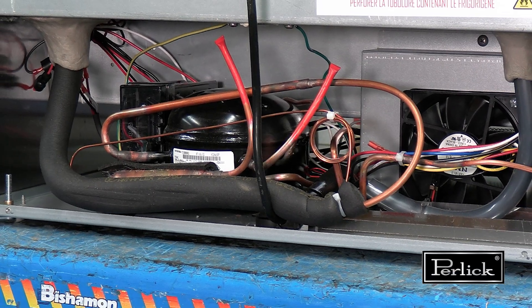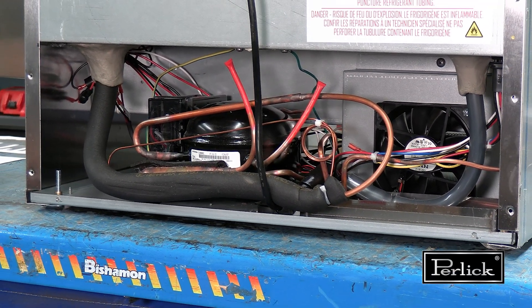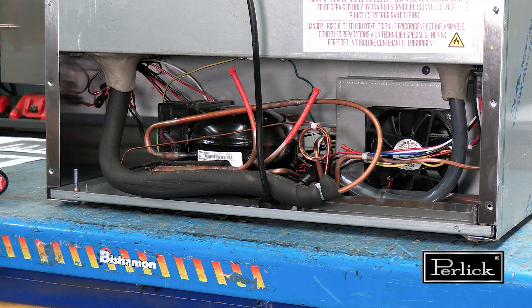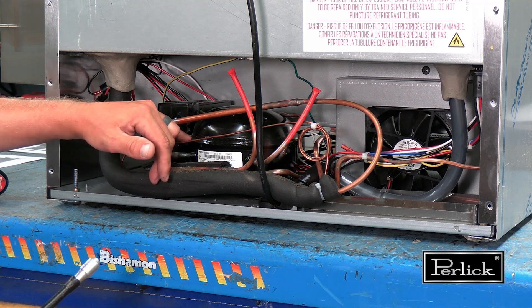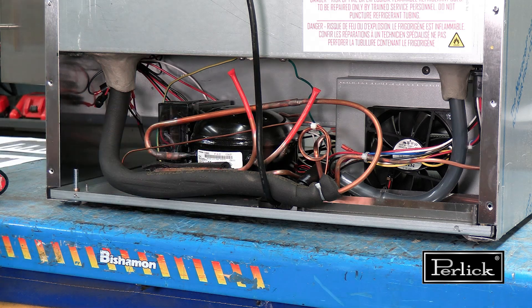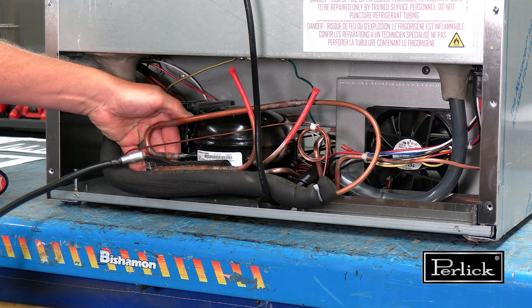The first step for evaluating a Perlick undercounter unit for a possible leak is performing a coarse search using an electronic leak detector. Scan around each braze joint, spending approximately 2 to 5 seconds and following the entire perimeter of the joint. Also evaluate the compressor crankcase sealing weld, any pipes going into the compressor shell, and all electrical posts. For hard-to-reach places, cup your hand to pool possible refrigerant leaks.